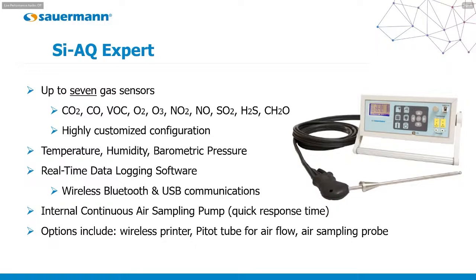We also offer an L-type pitot tube that connects to the two pressure ports on the face of the instrument. That allows you to insert the pitot tube into a flue or a duct to measure air flow and air velocity. You can also calculate volumetric airflow once you do that.